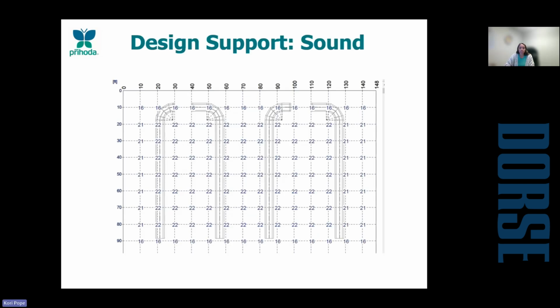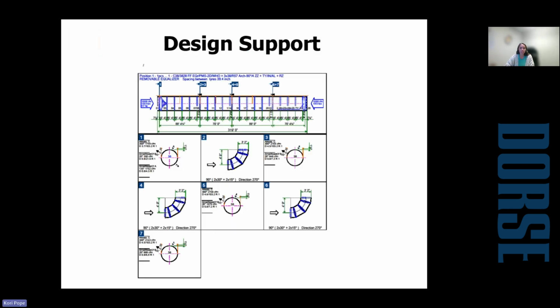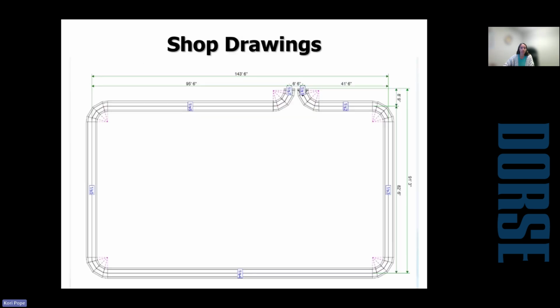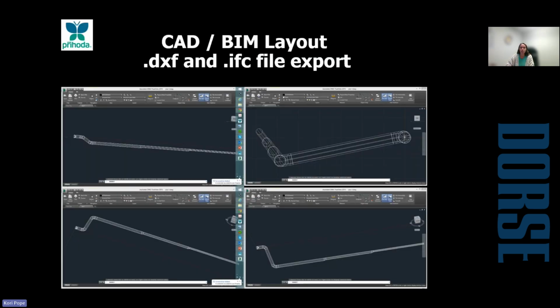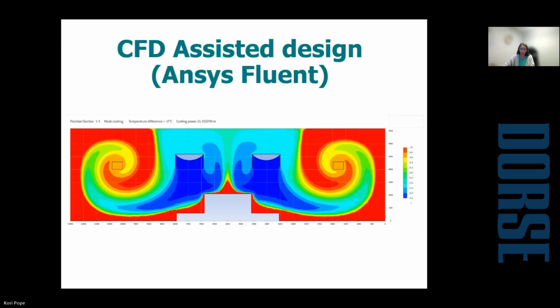So we can also put the duct systems into a virtual room so that we can see the sound levels at different distances and directions from the diffusers. So once this design is finished, the software has created fully dimensioned shop drawings that we can then export into any type of CAD or BIM layout so that these can easily be laid into the plans. For any supercritical applications, we can also provide a CFD.